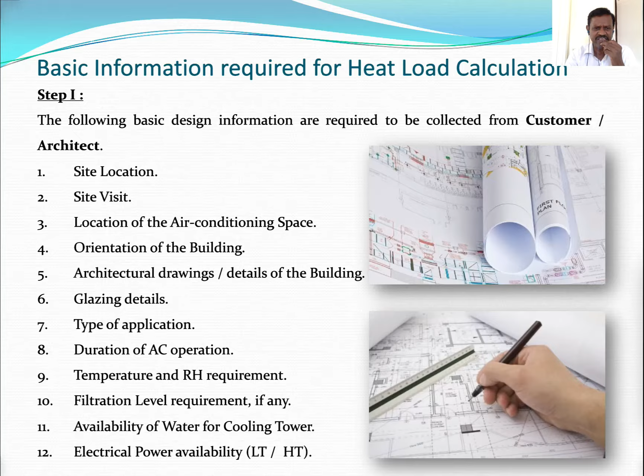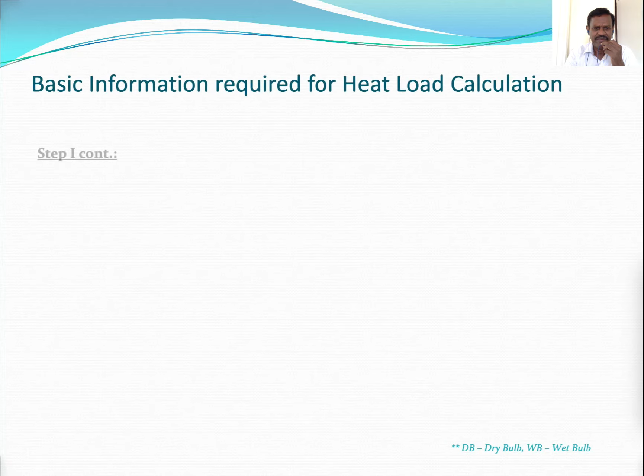availability of water for cooling tower, and electrical power availability, whether it is LT or HT. Now we will see it in a little more elaborate way. First one is site location. From the geographical location, because unless you know the location, you cannot decide the ambient conditions as per ASHRAE and ISHRAE. So site location is vital. That information you have to collect, and from ASHRAE or ISHRAE you can pull out the design ambient conditions. In India, May is the peak summer and our design is based on May.